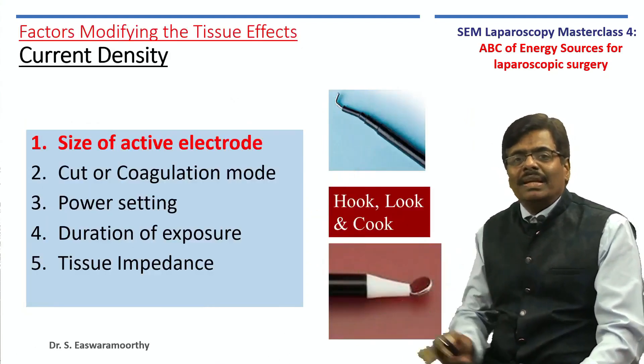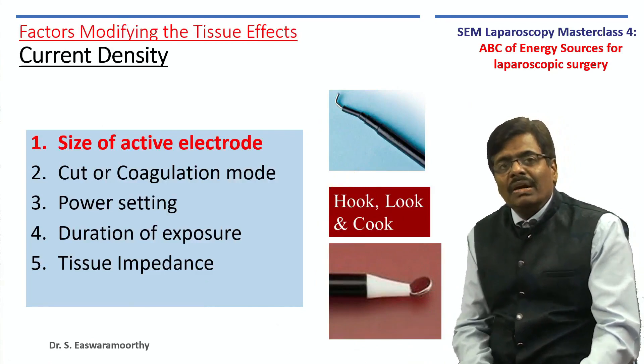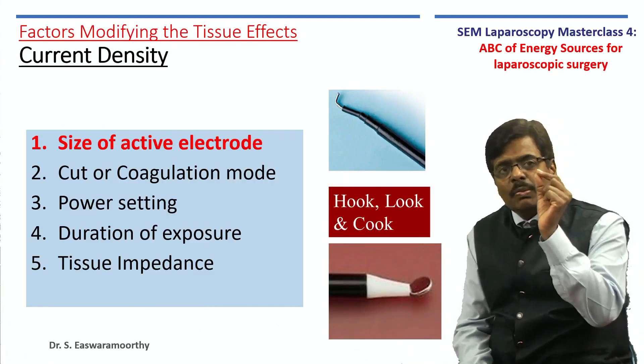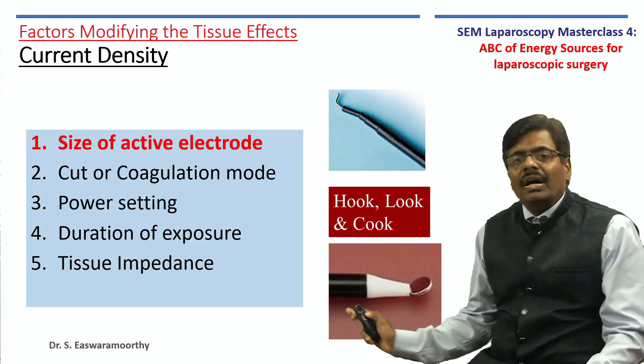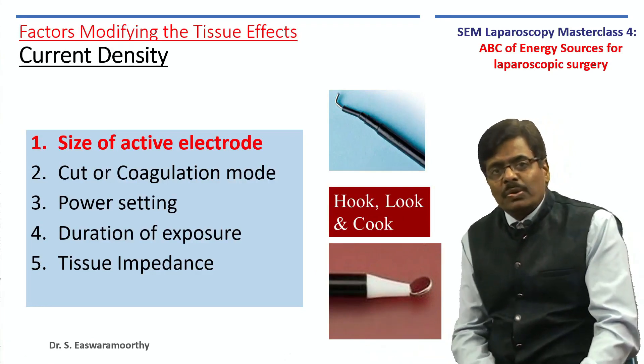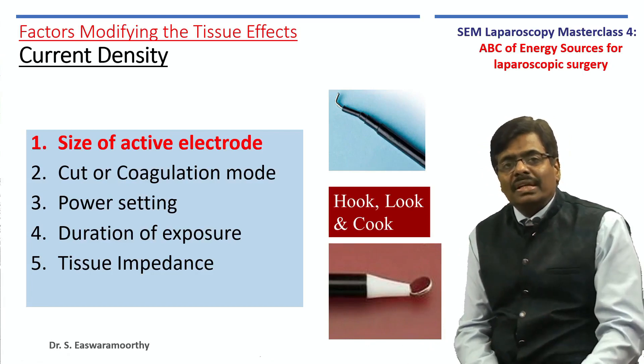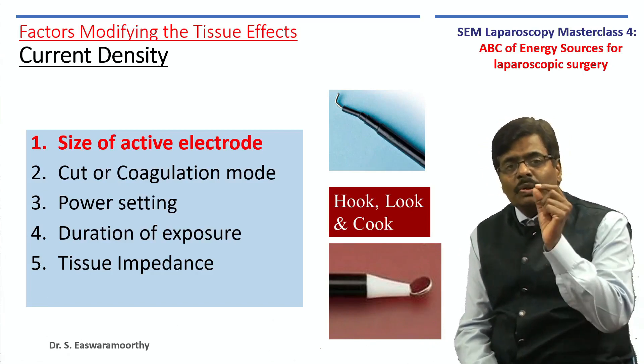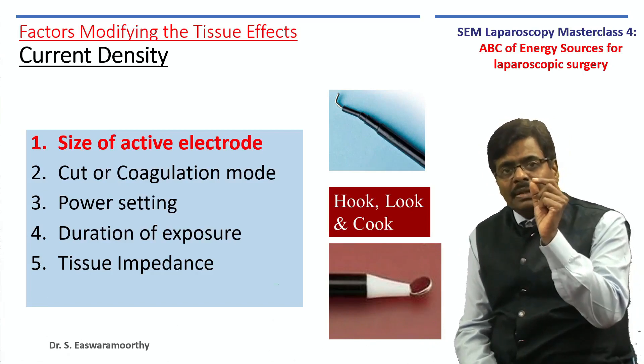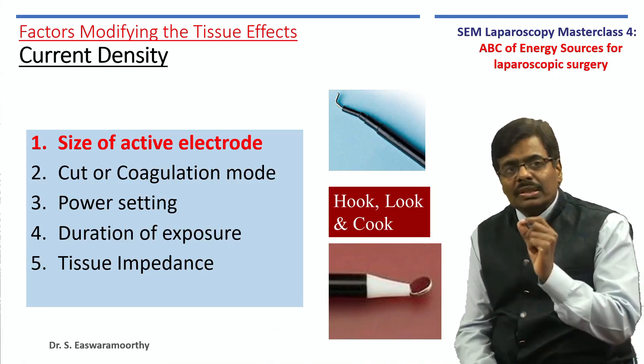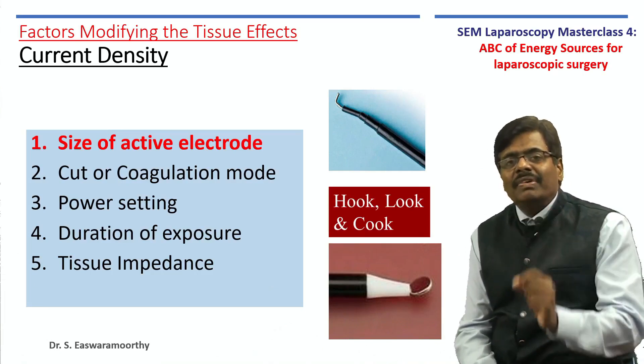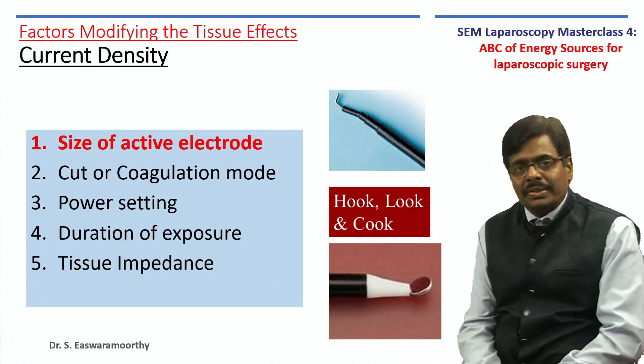For example, in laparoscopy, whether you use a small hook, the back of a spatula, or a curved dissector — which one gives a better, more precise diathermy effect? The hook, because of its smaller surface area. The size of the active electrode does matter.